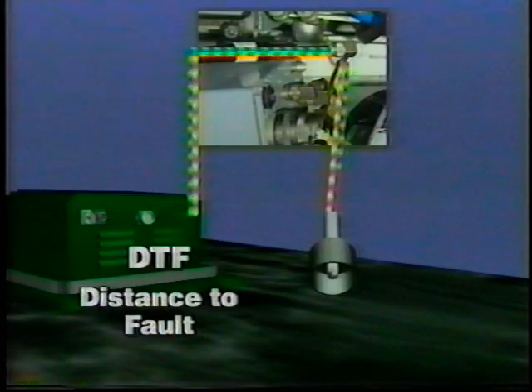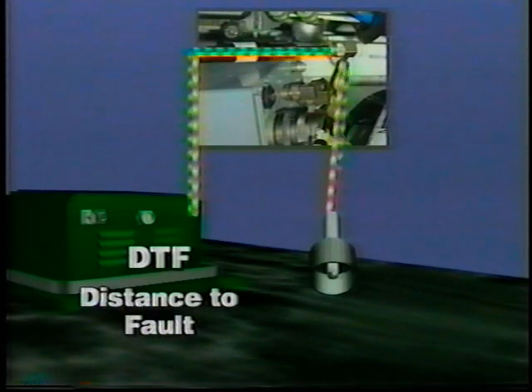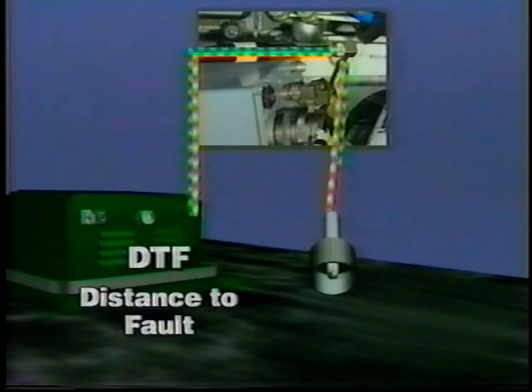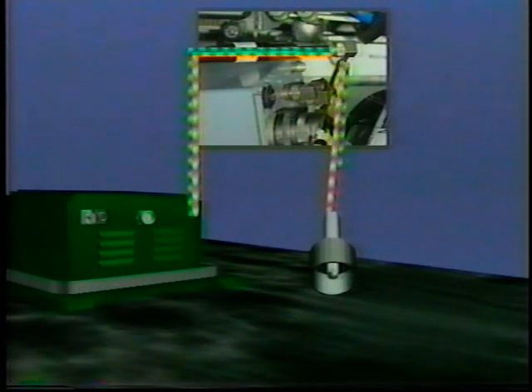For distance to fault, RFTLTS sends a ramped frequency through the line centered around the frequency identified as the problem. It then receives signal energy reflected back from the fault. By measuring the reflected signal, RFTLTS can determine the location of the fault.